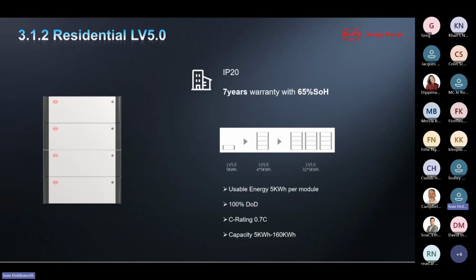So here we go. Here we can see the residential LV5, 5 kilowatt hours per module, and BYD, if you see 5 kilowatt hours on the nameplate, the usable energy is always the nameplate energy. So in each battery you get 5 kilowatt hours usable per module, and you buy the whole battery, you can use the whole battery, 100% DoD, and a C rating of 0.7. So the capacity is between 5 kilowatt hours and 160 kilowatt hours on a battery bank, and you can parallel between 1 and 32 batteries in a single bank, and you can stack them up to 4 high. It is a floor mount battery, and we'll get into more detail on how to commission those in a bit.